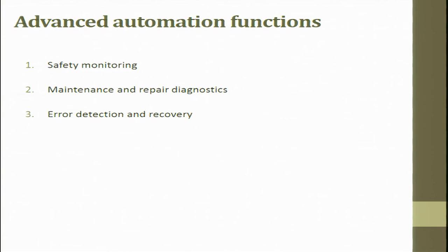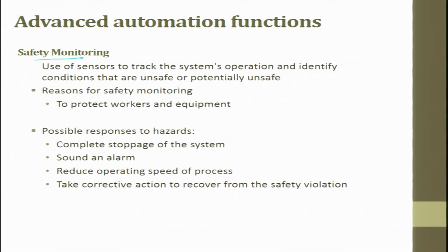Advanced automation functions include safety monitoring, maintenance and repair diagnostics, and error detection and recovery. Safety monitoring uses sensors to track system operation and identify unsafe conditions — for example, stopping the machine when a door is opened. Possible responses to hazards include complete stoppage, sounding an alarm, reducing operating speed, or taking corrective actions to recover from safety violations.